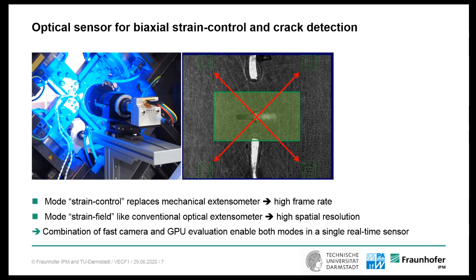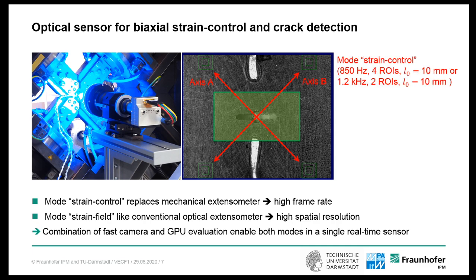The left image shows the DIC system in front of the bi-axial testing site. The DIC system basically consists of a fast CoaXPress camera, a telecentric lens, and a blue LED illumination. On the right side, you see the camera image. In the center, there is the starting notch for the crack, and at the corners, there are four regions of interest, which are in the same position as the tips of the mechanical extensometer. In strain control mode, the strain along axis A and B is measured between these ROIs. Depending on the field of view, we achieve measurement rates between 850 Hz and 1.2 kHz. For crack growth investigations, we use the strain field in the green area in the center.